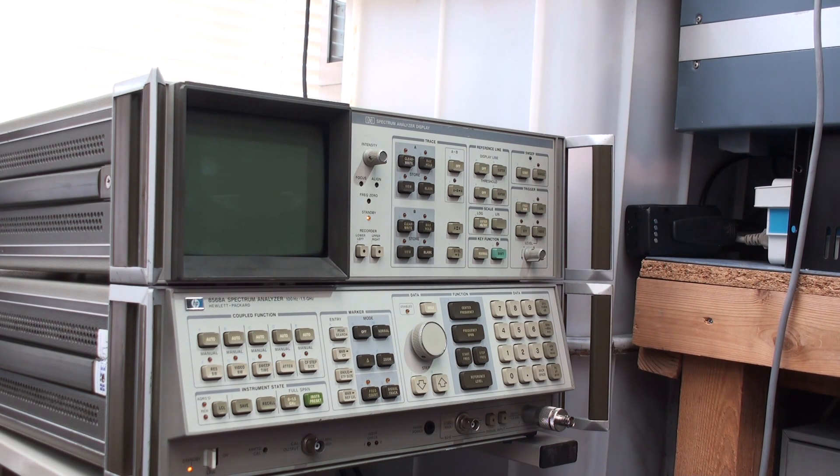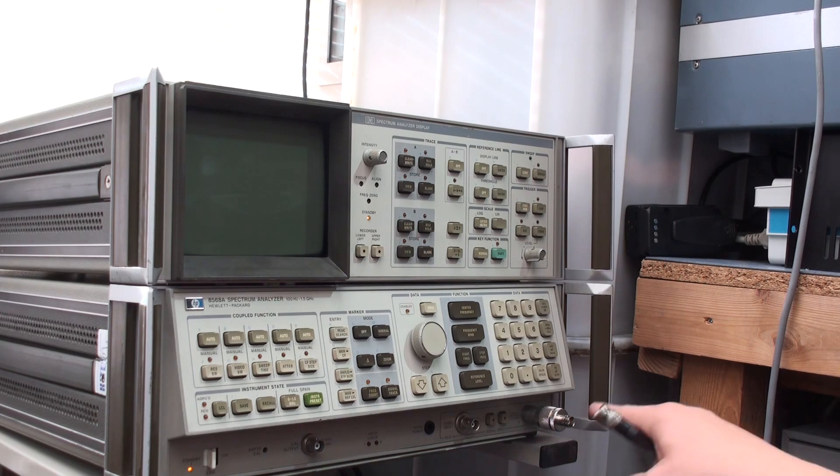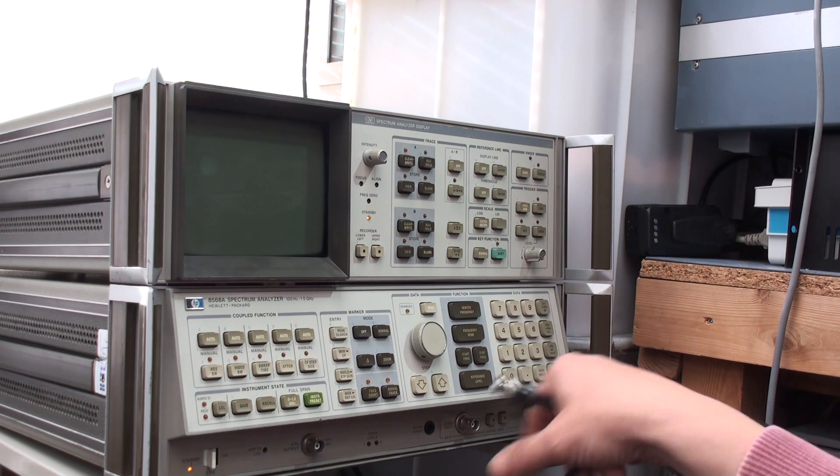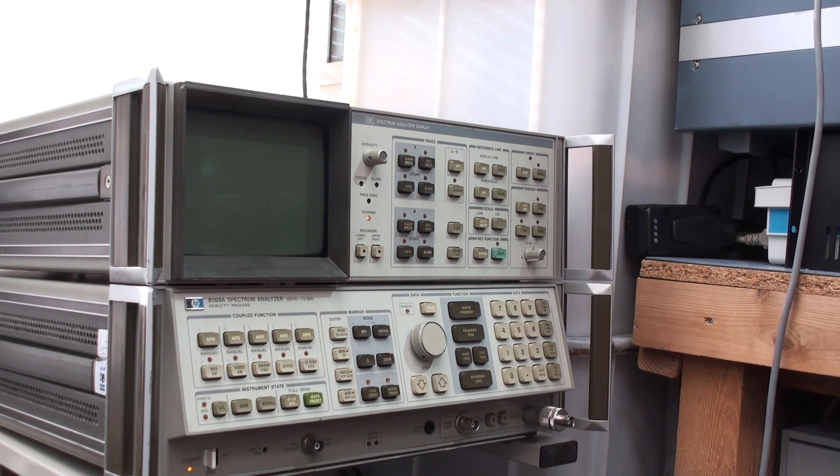Particularly this spectrum analyzer has caused a few problems. One of the faults it's recently developed is I can't do the calibration run anymore. There's a calibration routine where you take a minus 10 dBm output from the calibration socket here and feed it into its input and adjust this calibrator potentiometer to the correct level at minus 10 dBm.